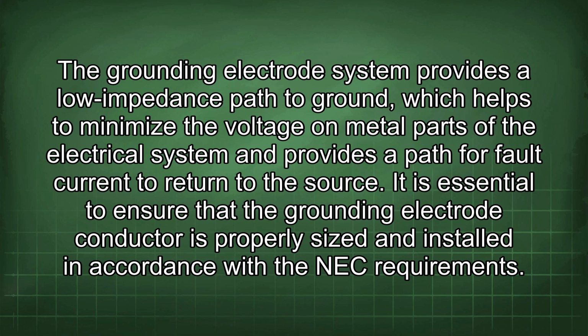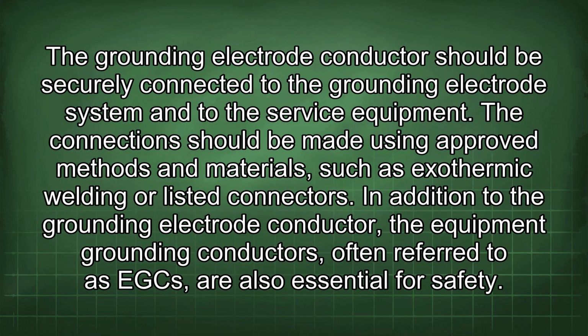It is essential to ensure that the grounding electrode conductor is properly sized and installed in accordance with the NEC requirements. The grounding electrode conductor should be securely connected to the grounding electrode system and to the service equipment. The connection should be made using approved methods and materials, such as exothermic welding or listed connectors.